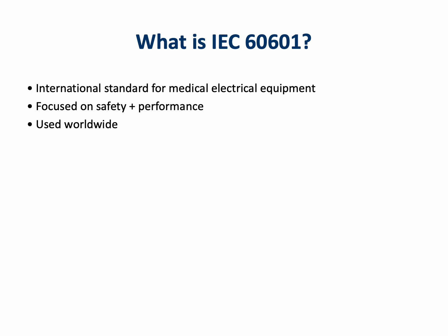By definition, IEC 60601 is the international standard that defines how medical electrical equipment must be designed and tested to make sure it is safe and effective for us to use. This is a globally recognized standard. And so if a device doesn't comply, it doesn't get to go on the market. So this is used worldwide, globally.